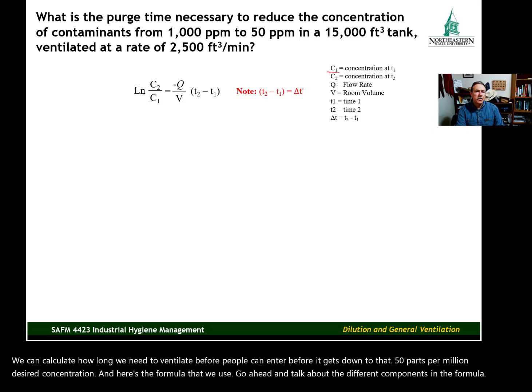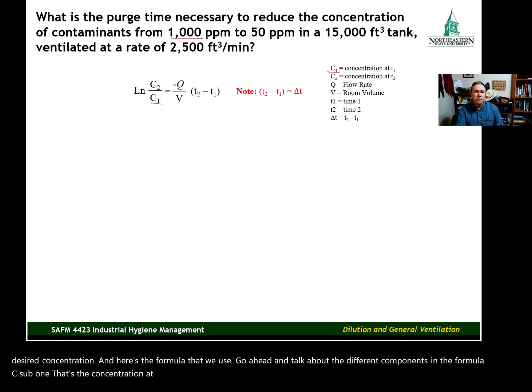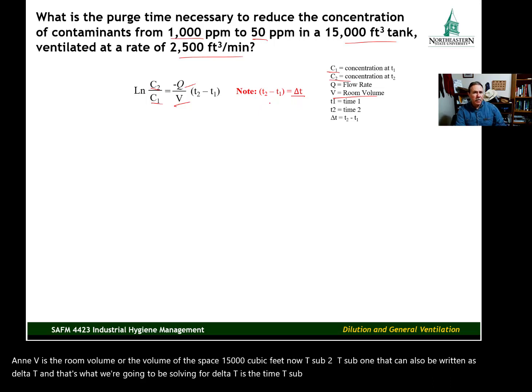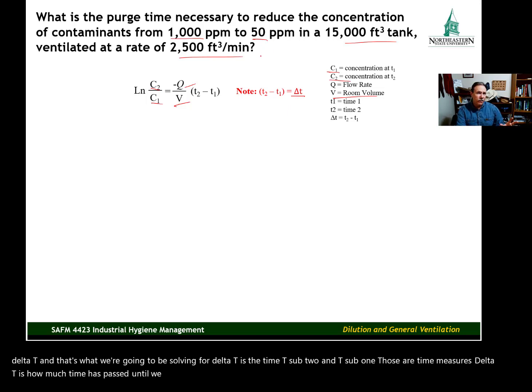C sub 1, that's the concentration at time 1, which is going to be 1,000. C sub 2 is the concentration at time 2, which is 50. Flow rate is 2,500 cubic feet per minute. And V is the room volume or the volume of the space, 15,000 cubic feet. Now T sub 2 minus T sub 1, that can also be written as delta T. And that's what we're going to be solving for. Delta T is the time, or how much time has passed until we reach the 50 parts per million concentration that we're shooting for.